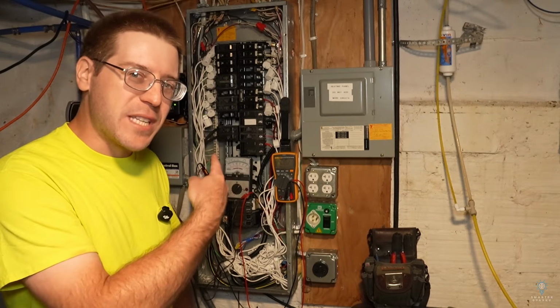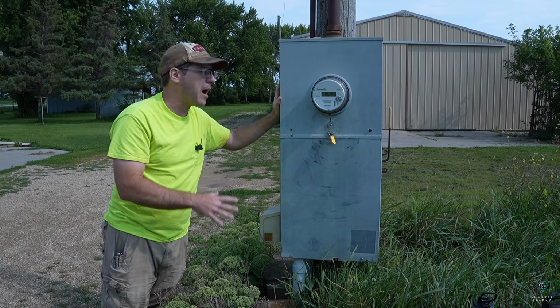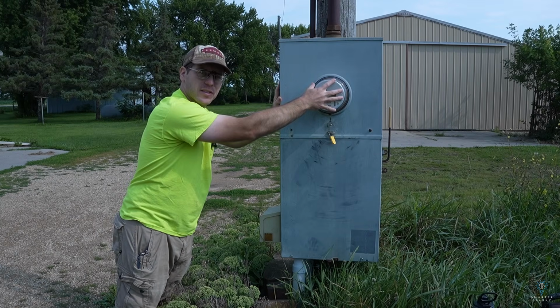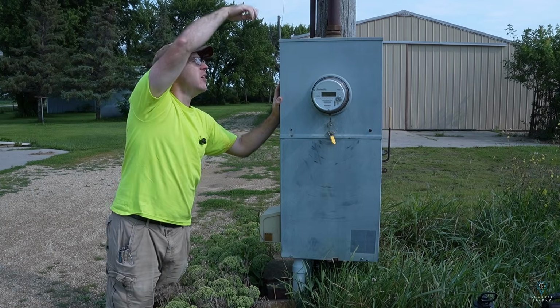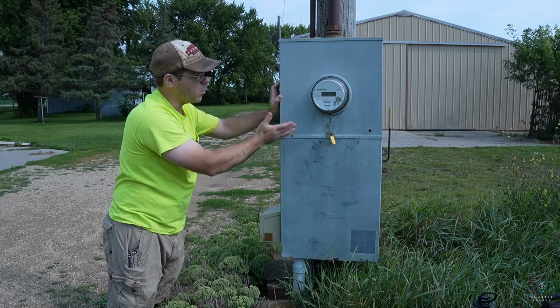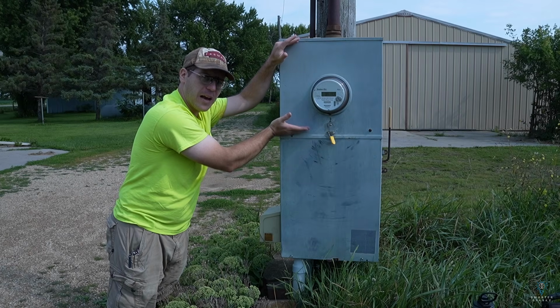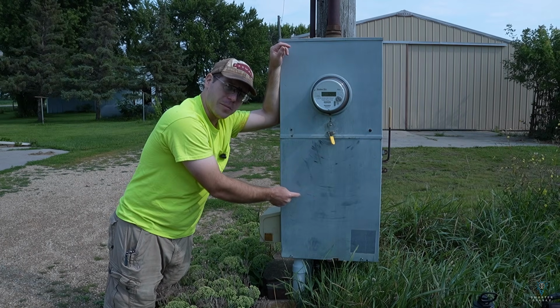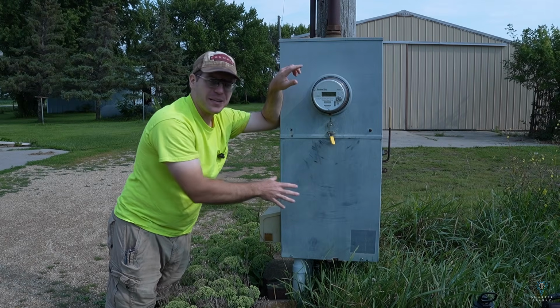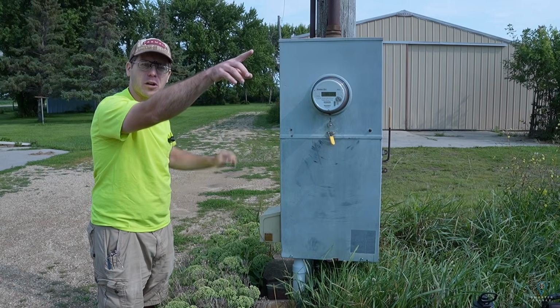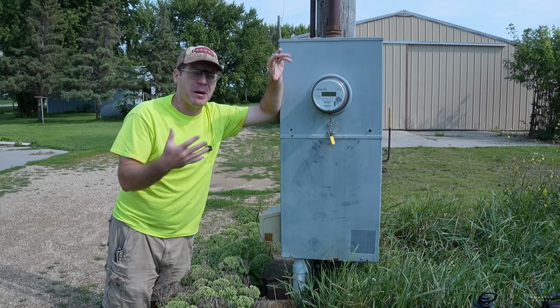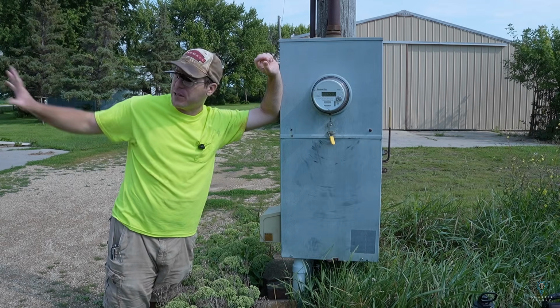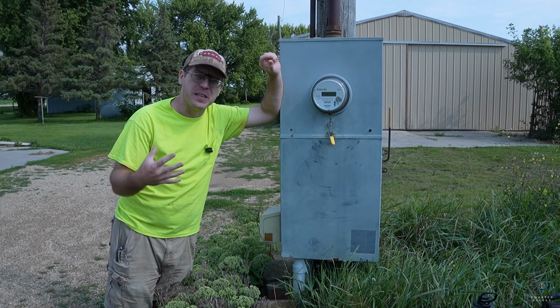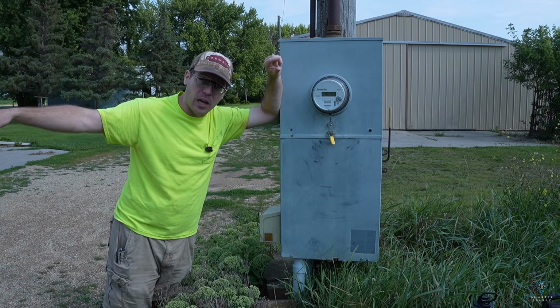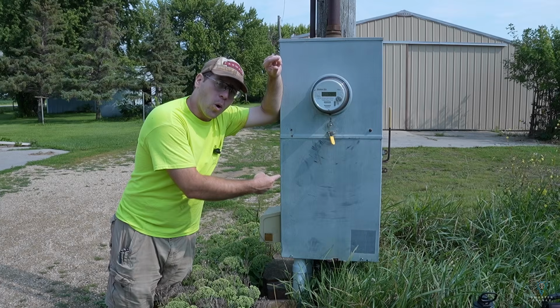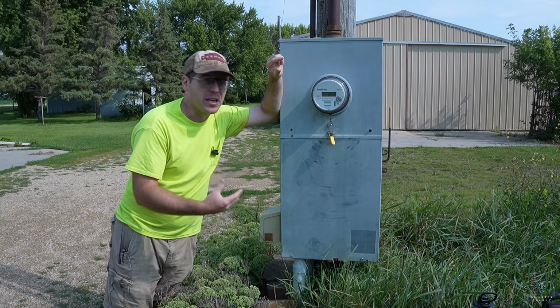I have a sneaking suspicion it's loose outside in the disconnect. So here's the main distribution point for my property. From up top in the pole down to the meter socket, that comes from the utility company. So across the street, overhead down into the meter socket, that is all power company owned. If we troubleshoot the issue into this top part of the cabinet, we're gonna have to call the power company. I am pretty confident the problem's gonna be down here in the customer side, because I do have another shed on the property and there's also a workshop over here. In neither of those buildings am I seeing those voltage drop issues. I'm only seeing those voltage drop issues over here at the house. So that tells me the common point for the house is either at the lug in the panel, which we just eliminated as being a problem, or where it's actually fed over here. That is my assumption as to where the issue is gonna lie.